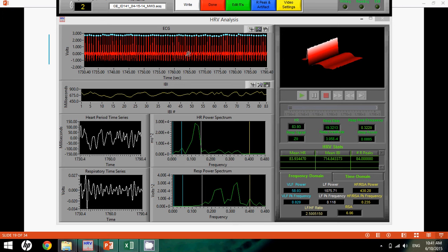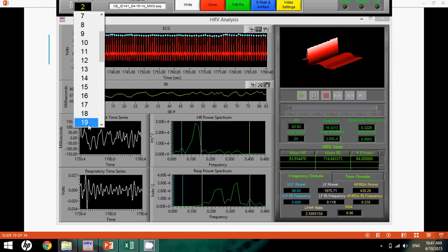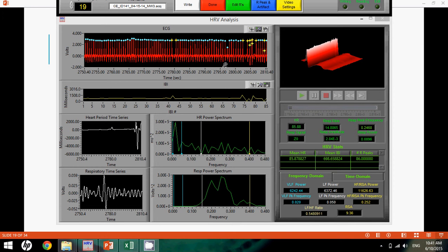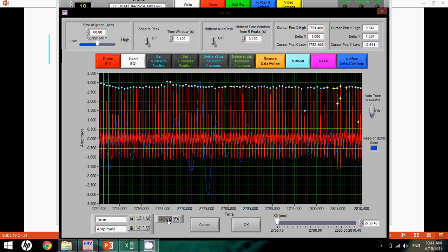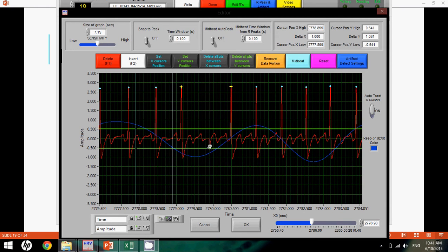And scroll through this data and see, I believe here on 19th. Indeed. So here we see that there are a number of issues. Again, we'll go here and look at this case. This is the perfect instance of what's called a packet drop. Basically what the issue is, is that the hardware was not communicating properly to the software.